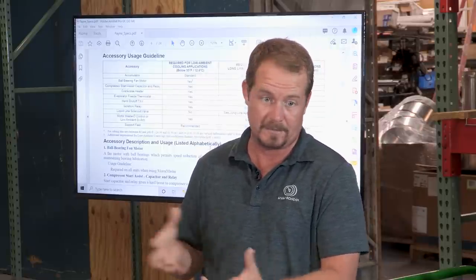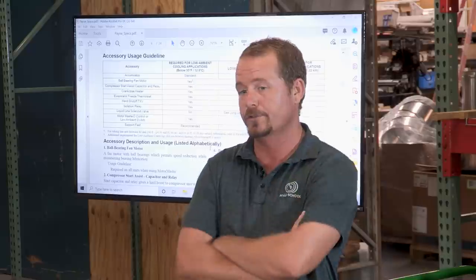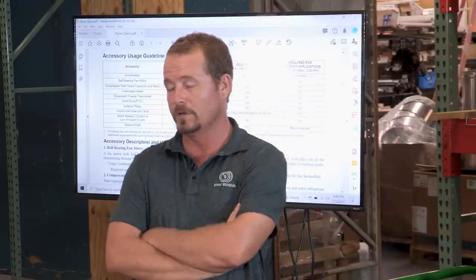The microfarads limit it. If you've done the underload test for capacitors, you've put your clamp on the start winding. About what is that current on average? Well, let's say between 4 and 6. The point is it's low. Why is it low? It's the start winding, right? And a lot of people say, well, the start winding comes out of the circuit. No, it doesn't. Not in a PSC motor.